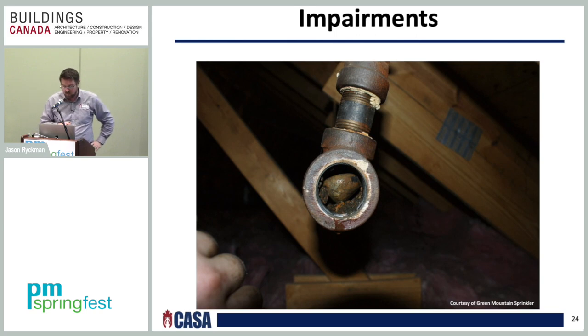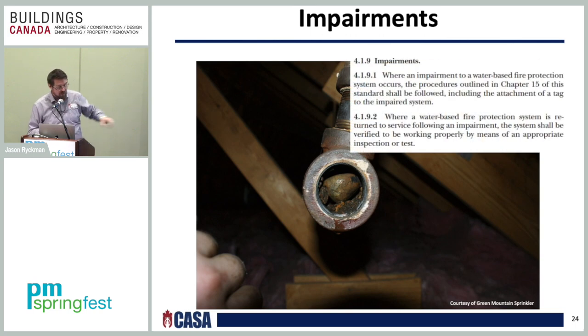Also, where an impairment to a water-based fire protection system occurs, the procedure is outlined in Chapter 15 of NFPA 25 and shall be followed, including the attachment of a tag to the impaired system. So whenever your system is impaired, there has to be a tag at the sprinkler valve and at the FDC stating that it's impaired, and all those directives are in Chapter 15. And there's what Chapter 4, 4.1.9, says, which tells you to follow the procedures outlined in Chapter 15.